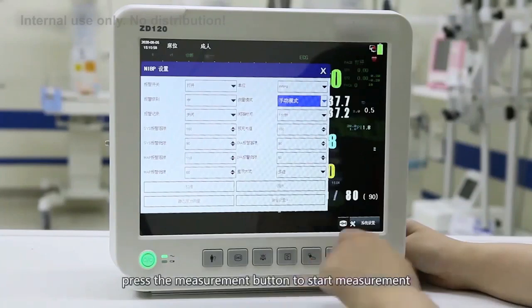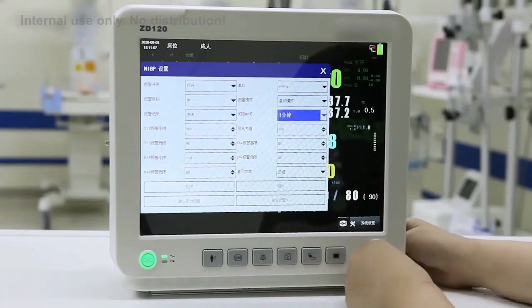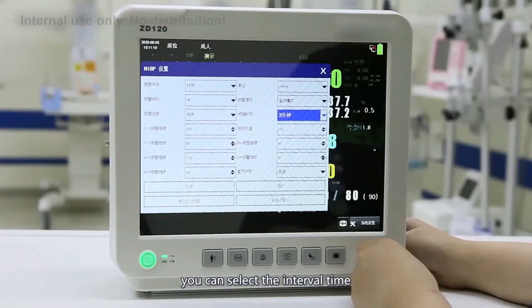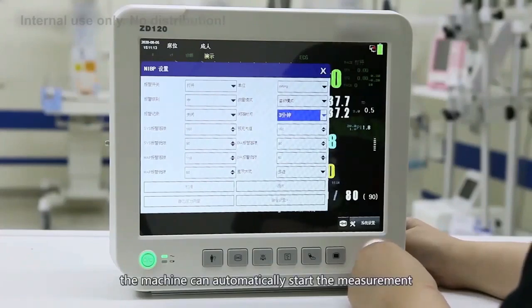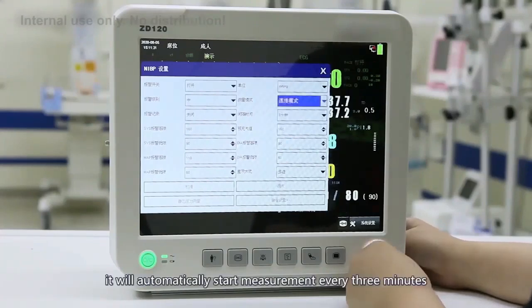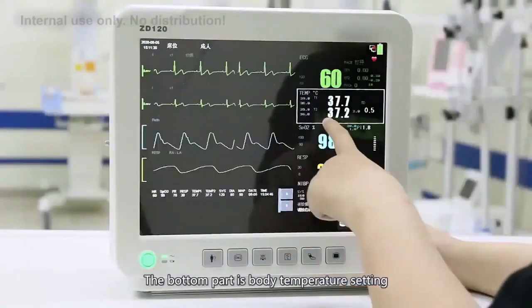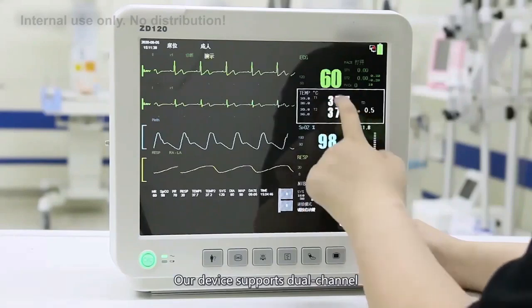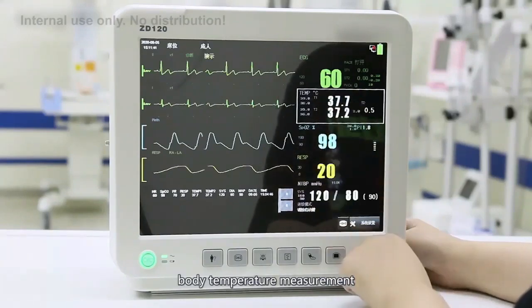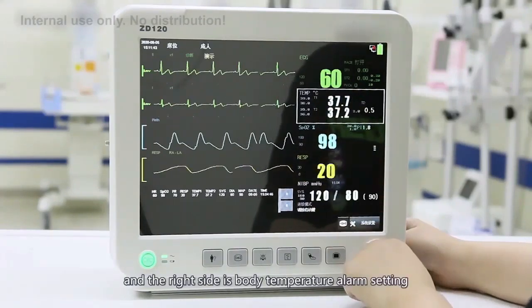There are 3 modes: automatic mode, continuous measurement, and manual mode. In manual mode, press the measurement button to start measurement. In automatic mode, you can select the interval time, and the machine can automatically start the measurement. Continuous measurement will automatically start measurement every 3 minutes. The bottom part is our body temperature setting. Our device supports dual-channel body temperature measurement. And the right side is body temperature alarm setting.